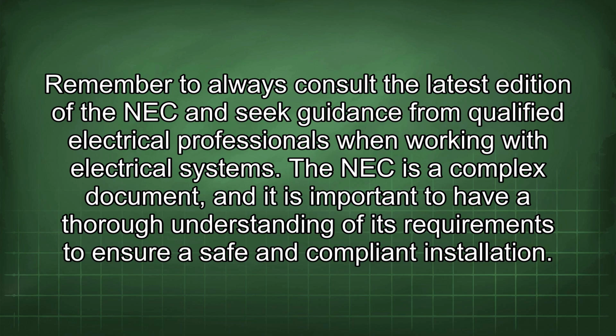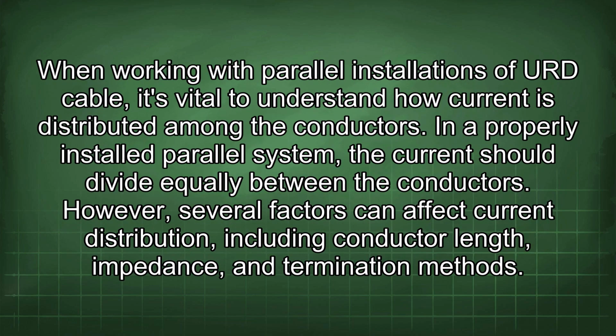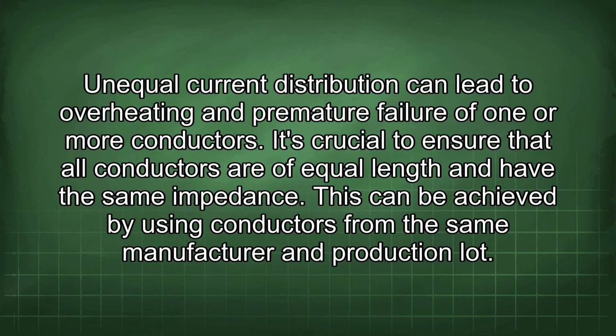Remember to always consult the latest edition of the NEC and seek guidance from qualified electrical professionals when working with electrical systems. The NEC is a complex document, and it is important to have a thorough understanding of its requirements to ensure a safe and compliant installation. When working with parallel installations of URD cable, it's vital to understand how current is distributed among the conductors. In a properly installed parallel system, the current should divide equally between the conductors. However, several factors can affect current distribution, including conductor length, impedance, and termination methods. Unequal current distribution can lead to overheating and premature failure of one or more conductors.